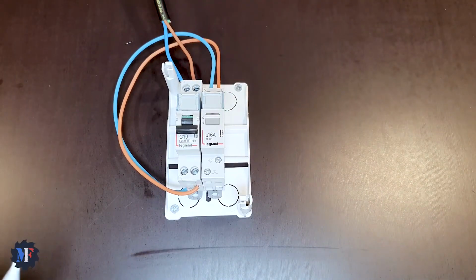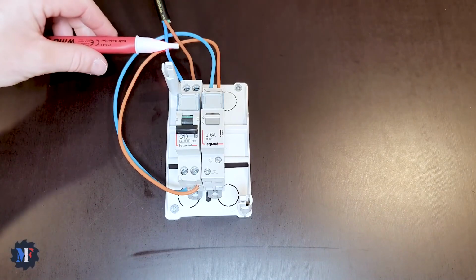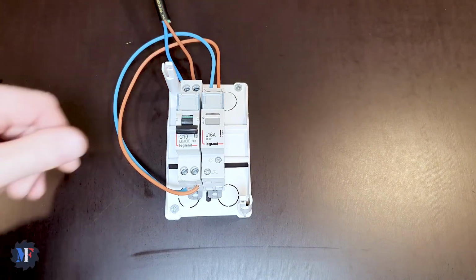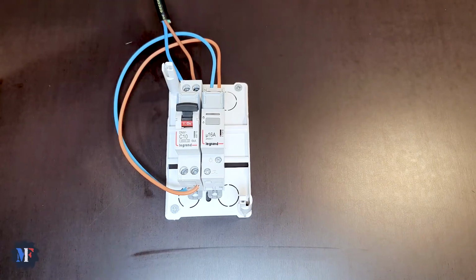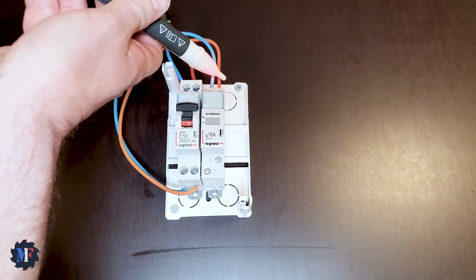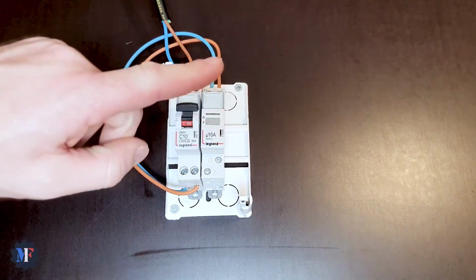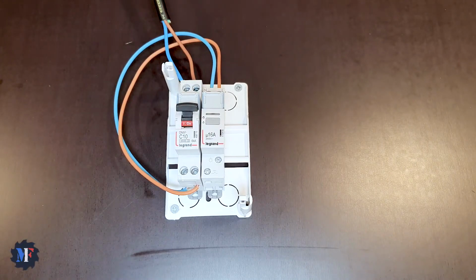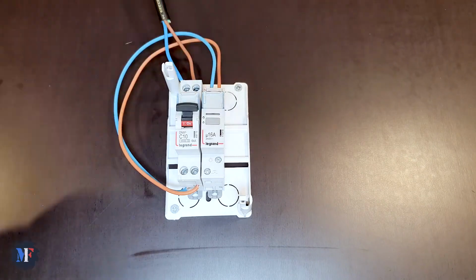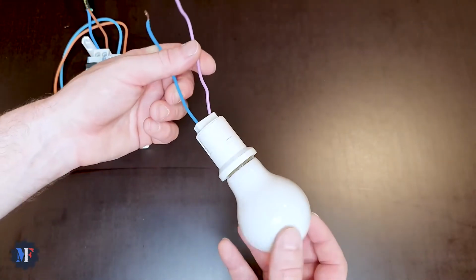So now I've connected everything, I've turned the power back on. Let's check that we have power here. We turn it on and normally here, look, it lights up, you see. So here the latching relay is powered by the 10 amp circuit breaker. I'm moving the camera back to give us space at the bottom and side so we can see the push buttons. So now that the latching relay is positioned in the panel, it's connected, we can take our light bulb again like earlier.